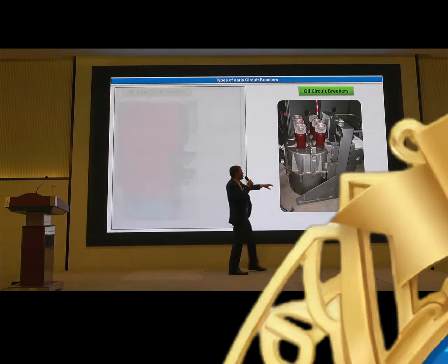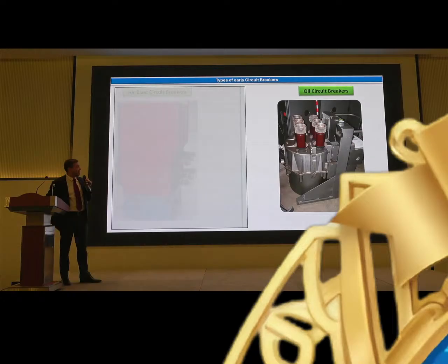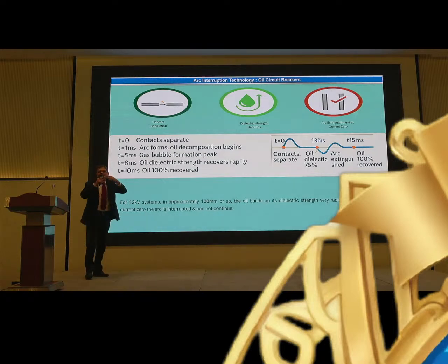Oil circuit breaker. Here, there was oil, not cooking oil, but of course insulation oil. So the current comes here, inside there is a contact, current goes out. At these joints, when I was separating the contact, an arc was happening, and the oil was quenching the arc, interrupting the current, not breaking, interrupting the current. So, a little bit of technical, very minor. Within 1 millisecond, you understand this is a very small time frame, the arc develops. Within 8 milliseconds, the oil regains its dielectric strength and quenches the arc. So this is how it was working.